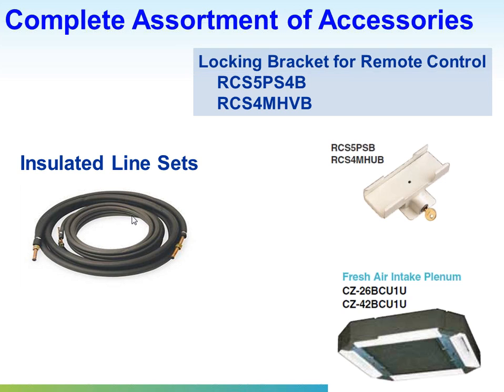Line sets. You must insulate. If you don't buy a ductless split line set as shown here, you must insulate both the liquid line and the suction line. These line sets typically come with flare fittings. One note of caution for the City of Chicago. City of Chicago does not allow mechanical fittings or mechanical connections. So a flare connection is a mechanical fitting. What they like to see is brazed line connections.